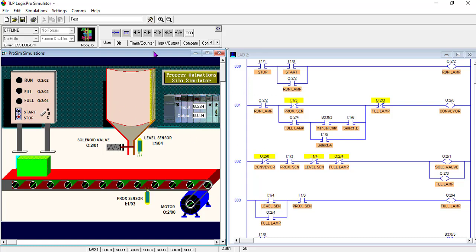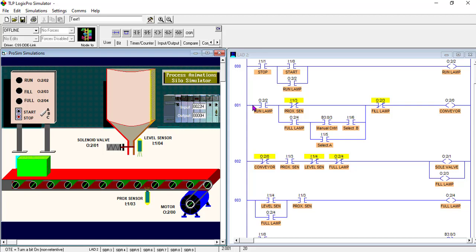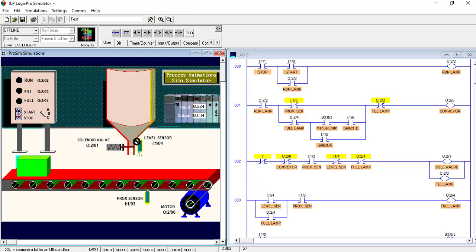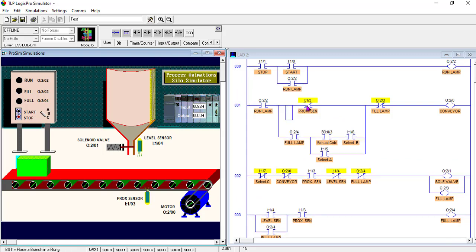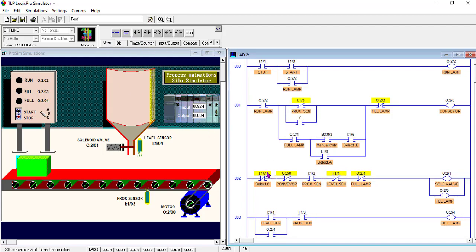I can also place interlocks to make sure that the switches do not misbehave. For C, because C just continues moving the box across the face of the silo - no filling, no filling is required - I'm going to put this contact here and call it C Select C. Then I will put a branch here to create a continuous bypass run with a C contact option, making sure that the belt continues to run without any problem.